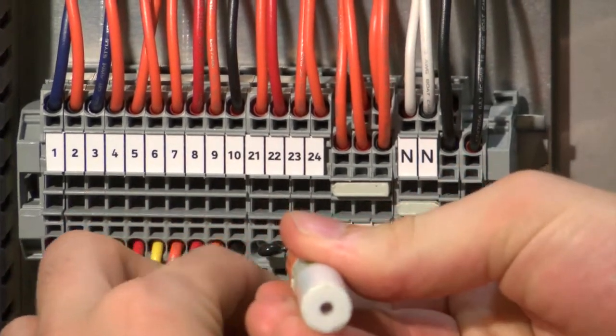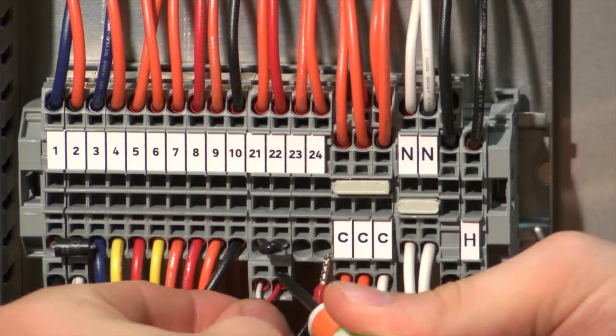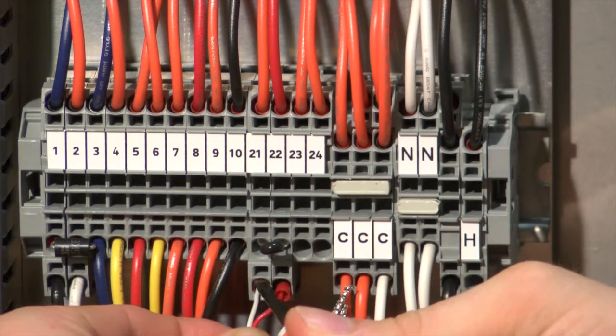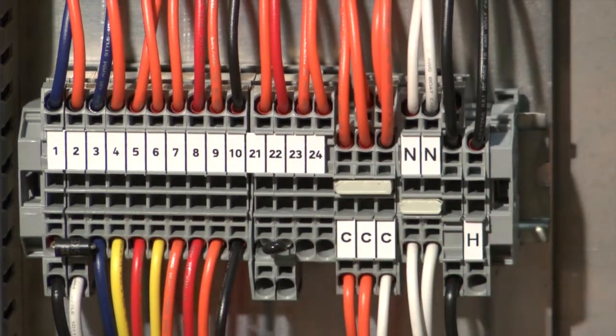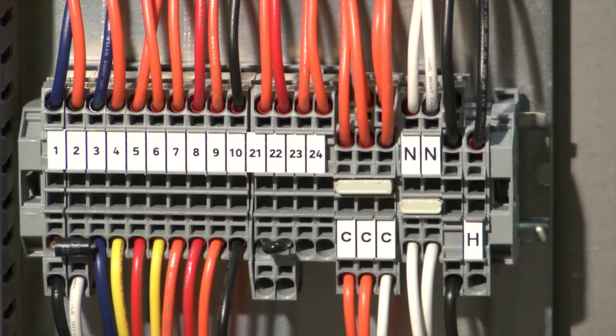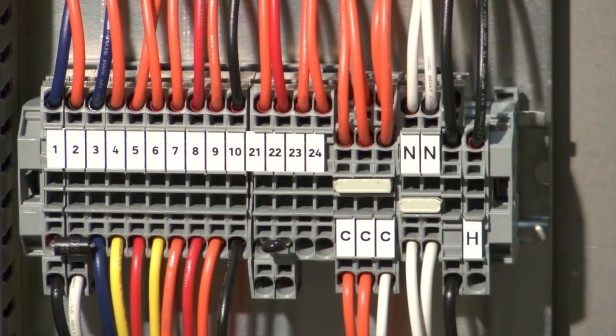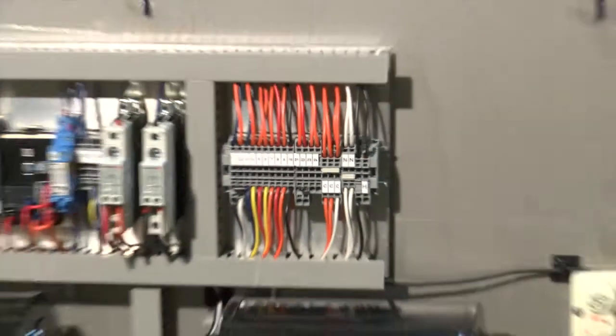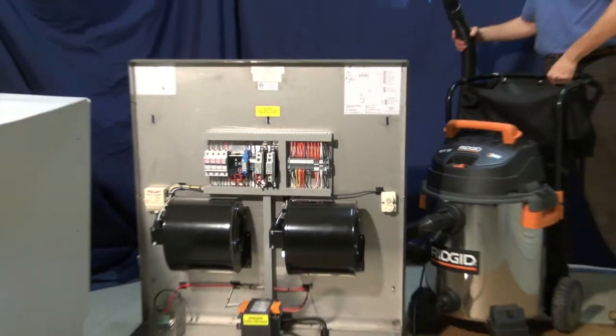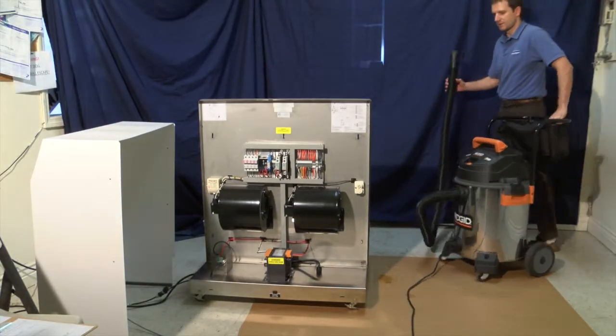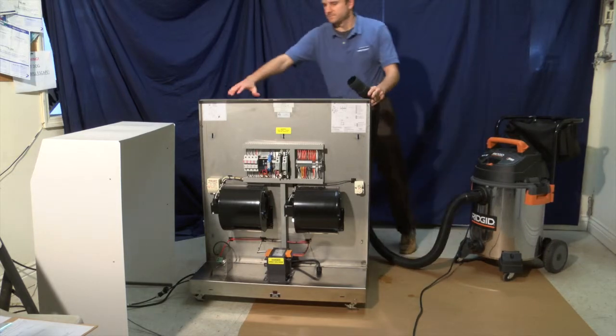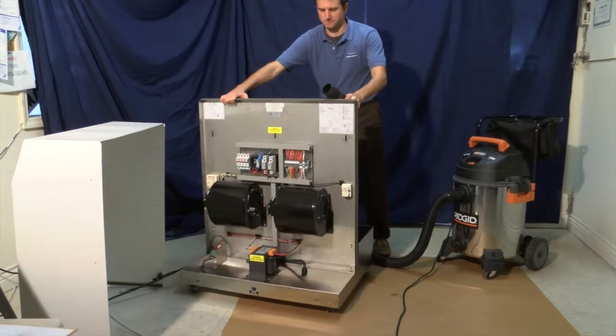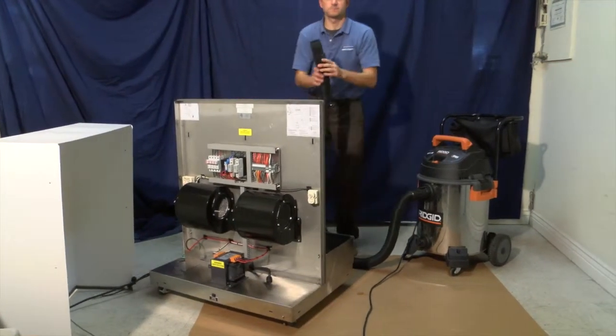You want to do this for all 4 wires that connect to the humidistat. After removing the wiring, you can set the fan cover aside to protect it. You're then going to want to remove the water from the water pan completely. A shop vac is the easiest way to perform this process.